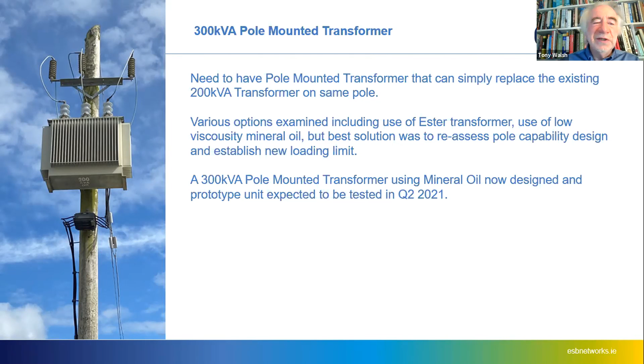So our solution is to develop a 300 kVA pole-mounted transformer of the same size, dimensions, and weight that's okay to fit on the existing pole. So for a 300 uprate of this transformer, we take down the existing one, put up the new one, and now we've 50% extra capacity for a very small capital cost, and we can do the job in maybe a day and a half.